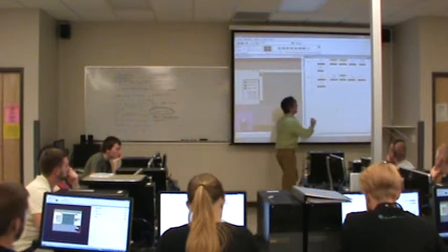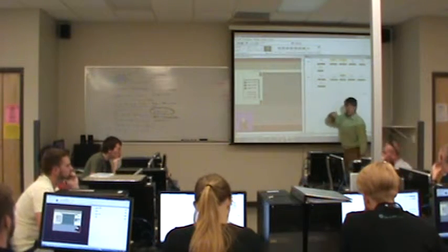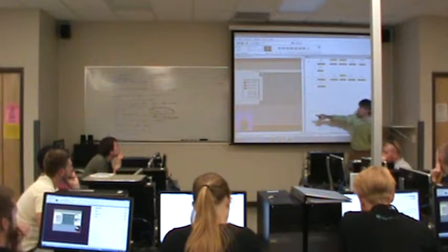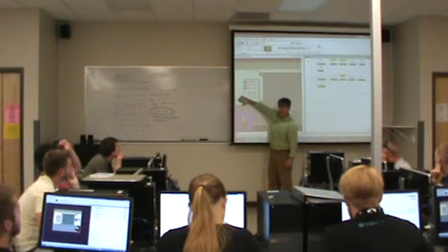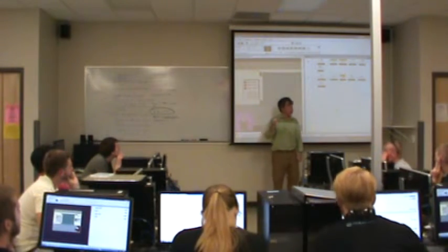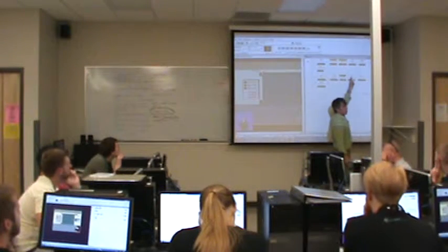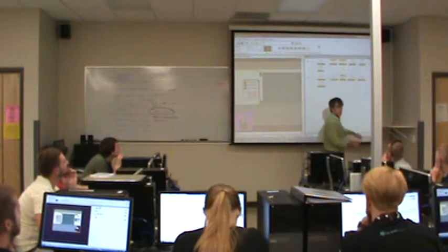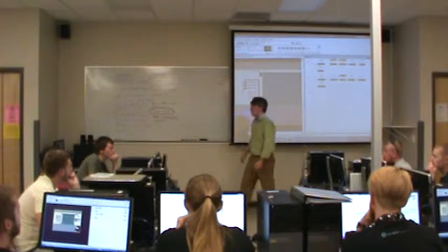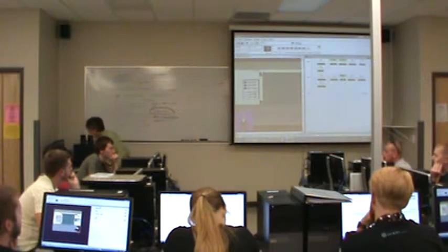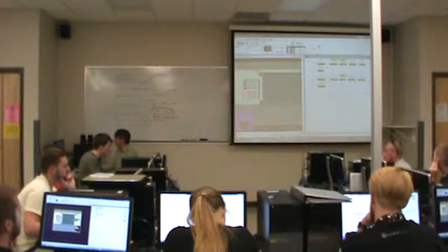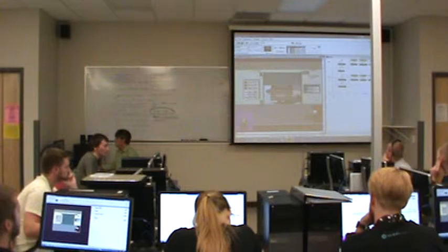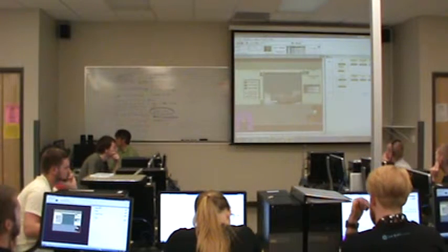Since that bit is on, and this instruction looks at the address that the button's connected to, it's going to find a 1 there, and that's going to pass power. When the button is active, in other words, when the button is being pressed, the switch will no longer pass power. That will put a 0 into address 1/2, which means that this set of contacts will open up, cut that off, which will break the seal. Okay, so the stop button will stop the motor from moving up or down, because I put an instruction on both fronts. So let's download it, run, see if it works. All right. Open, stop, close, stop. It does work. Good.